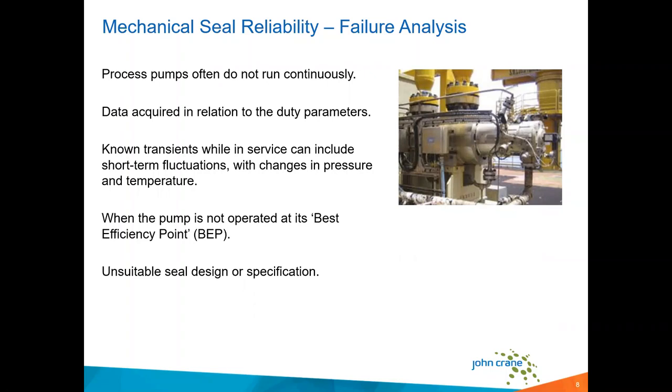Certainly when we're considering equipment reliability, and principally mechanical seal reliability, following a failure we really want to obtain necessary data related to that failure. If we're objective and aware of this information, we should be on the right path to resolution. We want to consider several points when looking at relevant data for the application. Process pumps often don't run continuously, which can lead to uncertainty about actual cumulative operating time and the number of start-stops which occur. All this information is helpful to understand the seal performance criteria and to evaluate the seal reliability overall when we look at that specific failure.